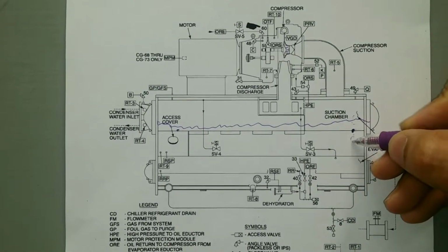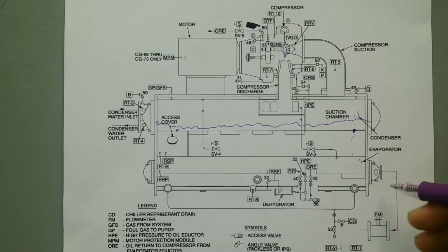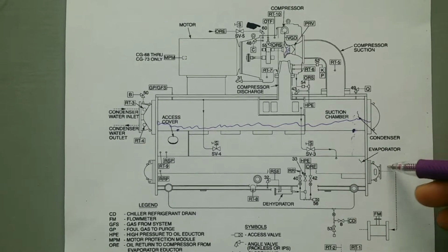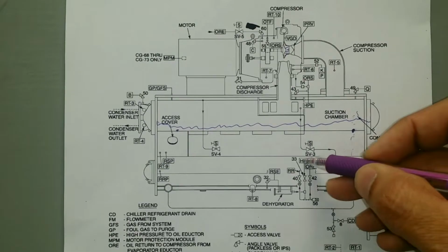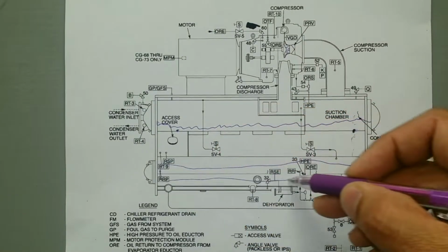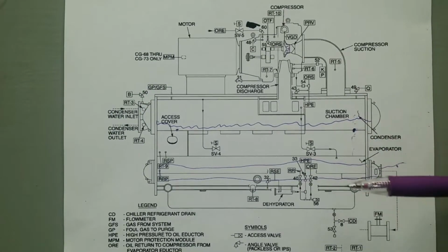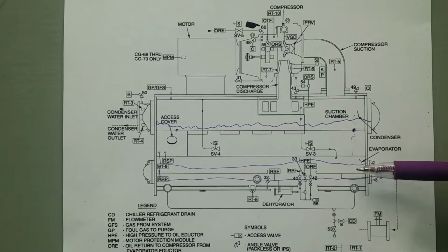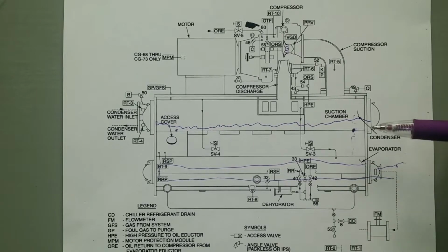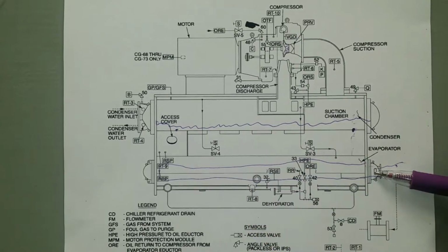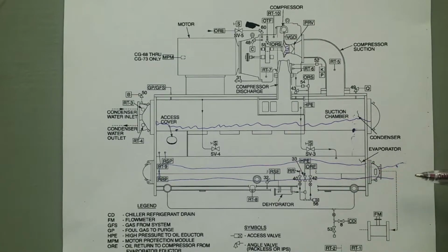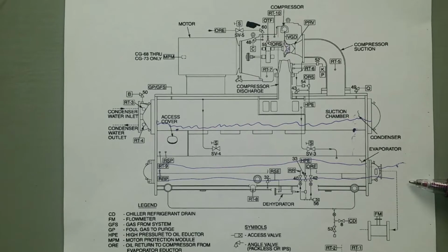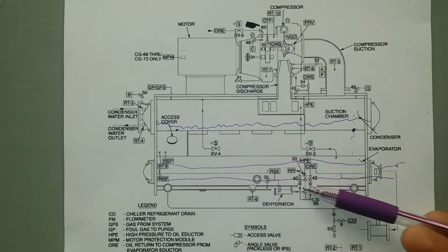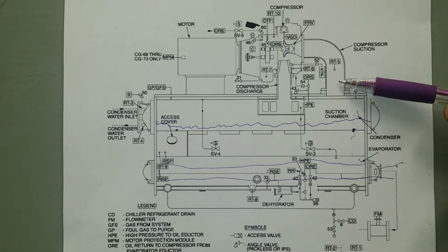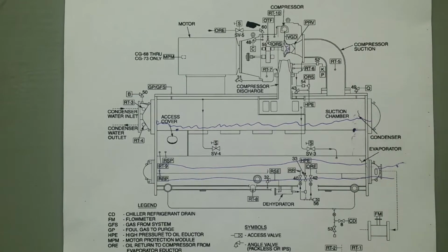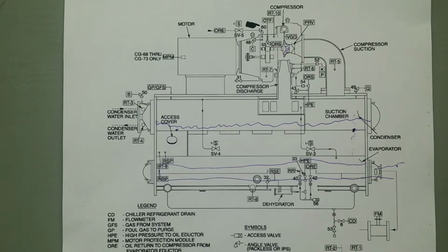Anyway, as the refrigerant meters out into the evaporator, in the evaporator you've got chill water over here that is coming in somewhat warm. It goes into pipes or tubes, and it turns around and goes right back out the same place. But now the outside of those tubes is where the liquid refrigerant starts touching it, and it flashes into a vapor, and it removes heat from the chill water. So the chill water leaves colder, and then all of that gas gets piped all the way back into the compressor to be sucked in, and the cycle repeats itself.